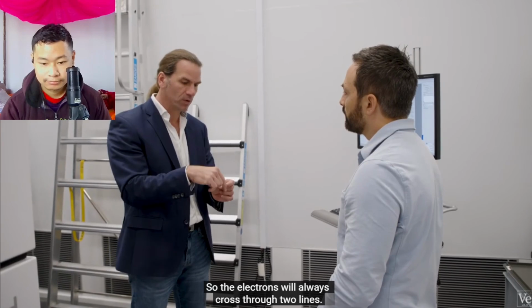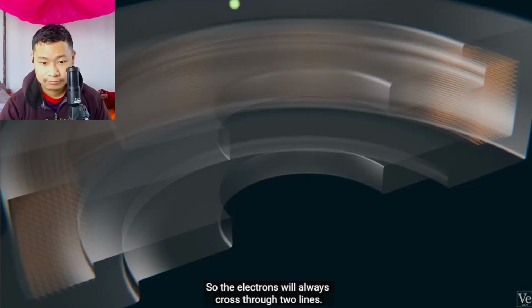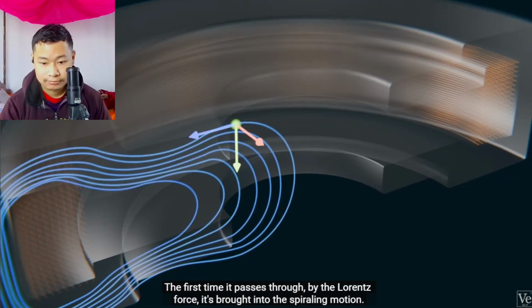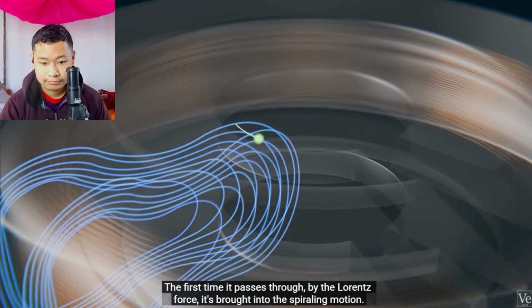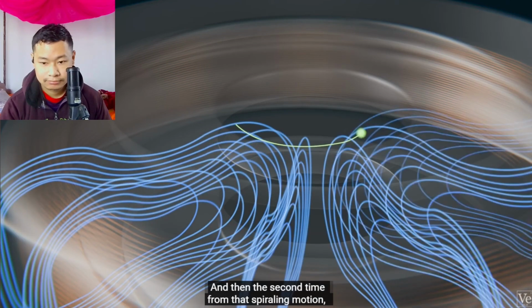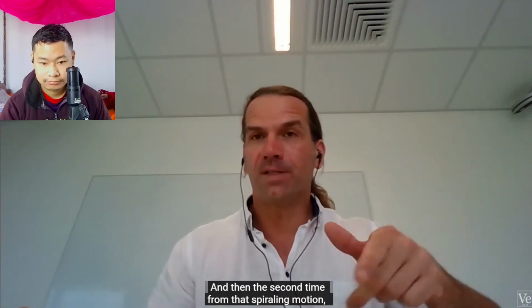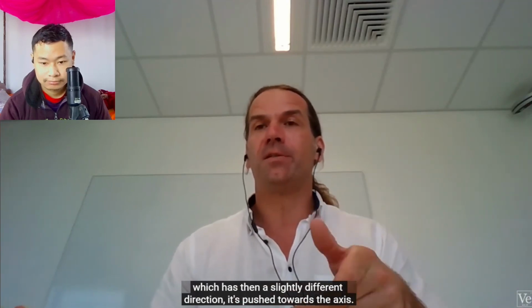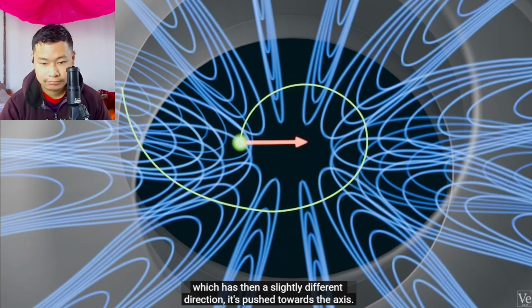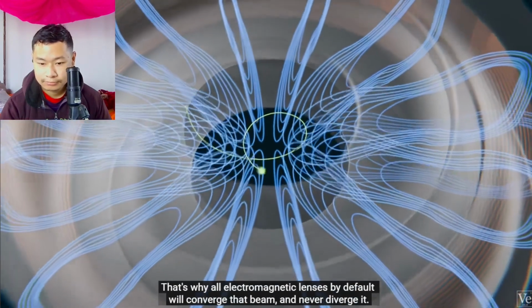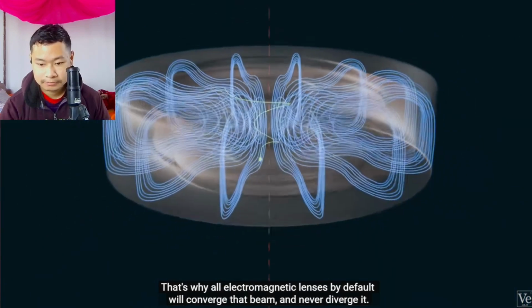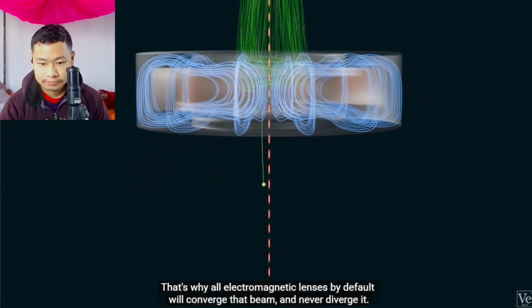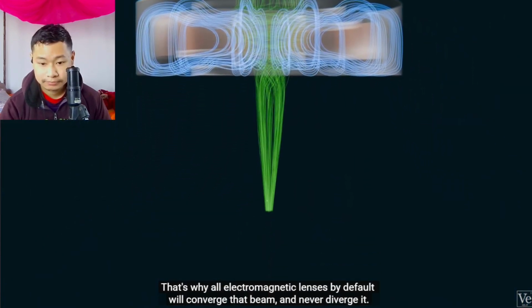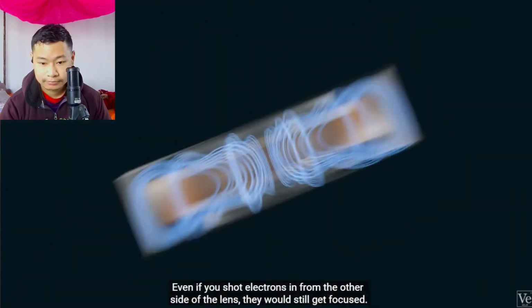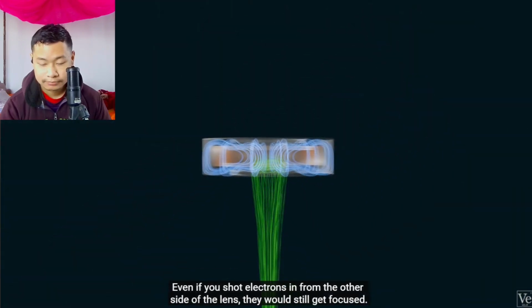So the electrons will always cross through two lines. The first time it passes through, by the Lorentz force, it's brought into a spiraling motion, and then the second time, from that spiraling motion, which has a slightly different direction, it's pushed towards the axis. That's why all electromagnetic lenses, by default, will converge the beam and never diverge it. Even if you shot electrons in from the other side of the lens, they would still get focused.